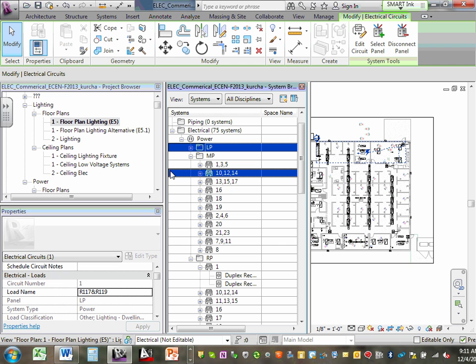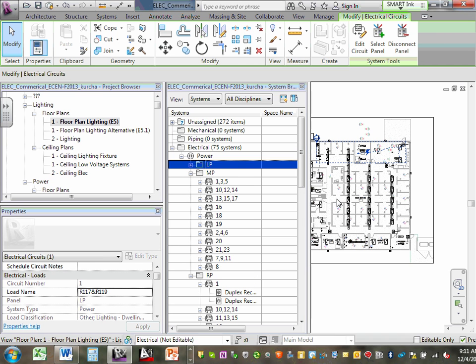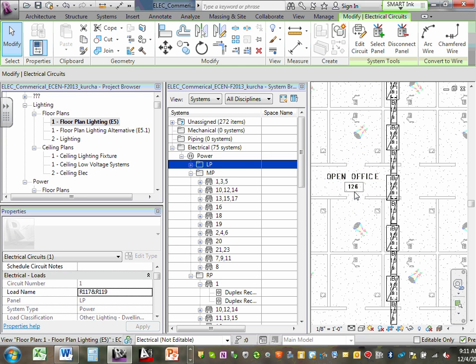For example, in the open office, if I have a light or receptacle in the open office, I would say R126, east wall, west wall for the receptacles, north wall, south wall. So use these terminologies so you can identify them in a bigger area. When you have a lot of circuits, make sure you use them, or a cubicle, right? The north cubicle, south cubicle. You know what I mean? Give enough information to know where the circuit is.